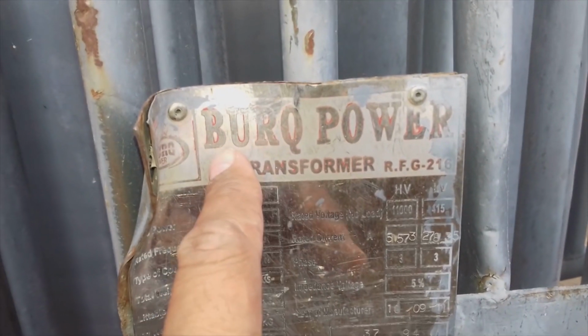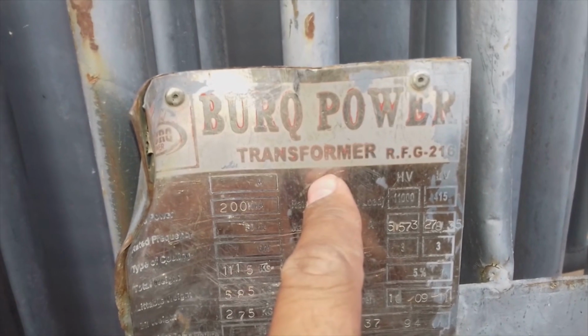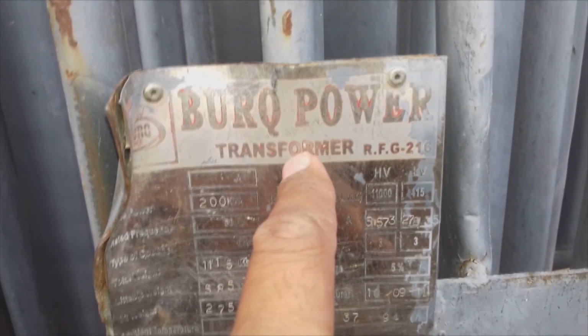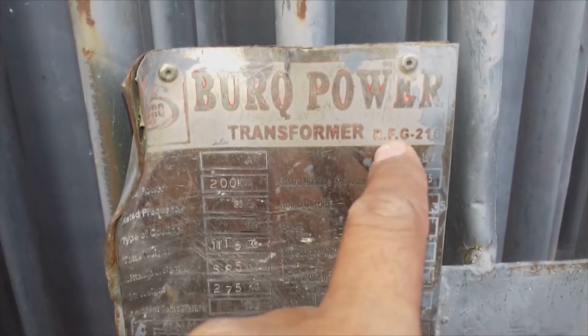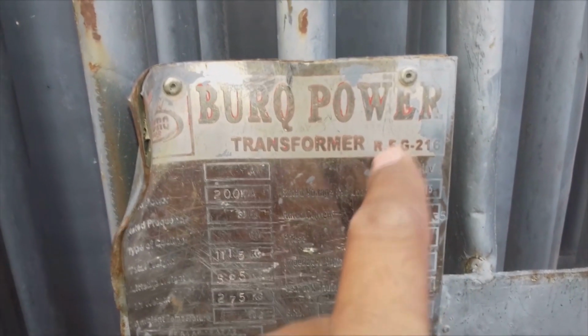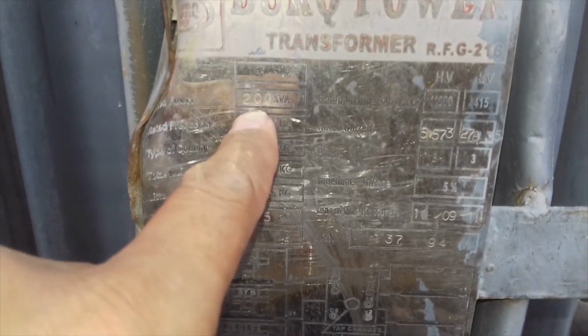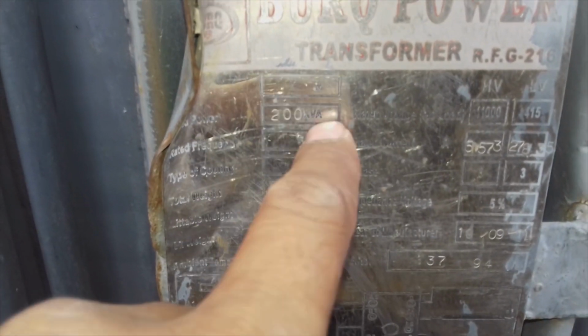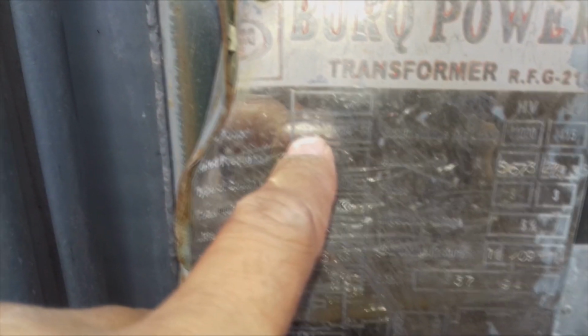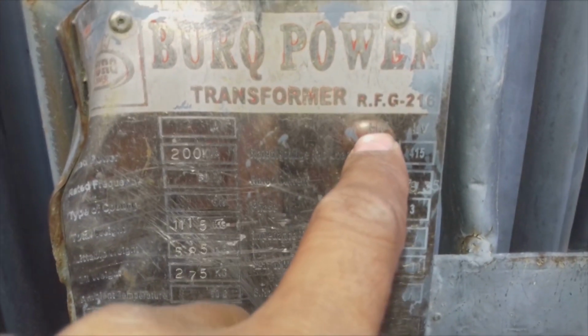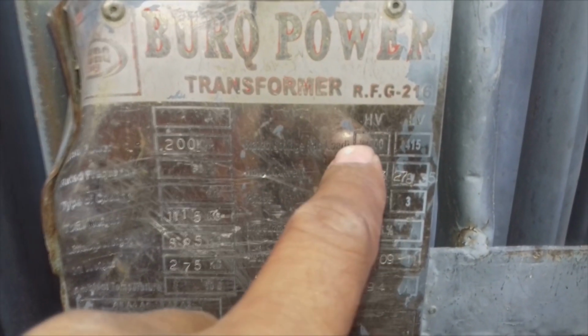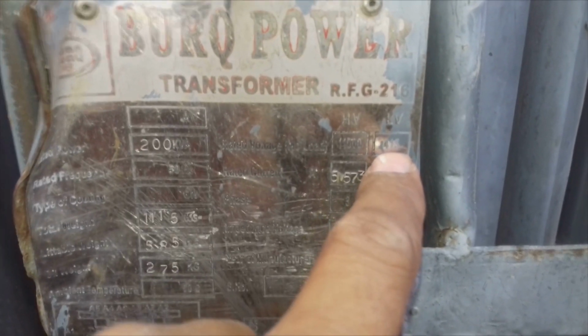So here is this transformer nameplate you can see, which is very common for each and every transformer, and they have written some parameters. First, you can see the Burq Power transformer. This is the manufacturer for the transformer, and here is some manufacturing model number they have given. And here you can see this is the rating power, which is written 200 kilovolt ampere, 200 kVA of course, and this is not in kilowatt. So here is the input or primary voltage, which is 11,000, and the secondary voltage is of course 415 volt.